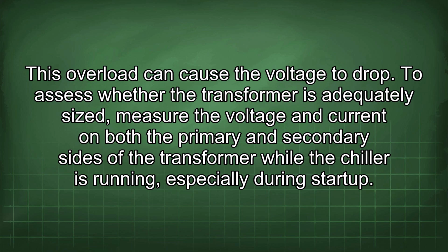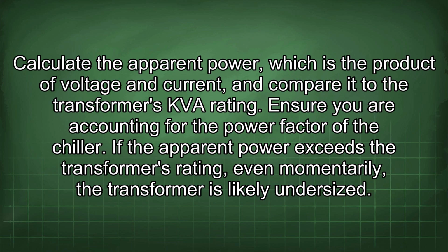To assess whether the transformer is adequately sized, measure the voltage and current on both the primary and secondary sides of the transformer while the chiller is running, especially during startup. Calculate the apparent power, which is the product of voltage and current, and compare it to the transformer's kVA rating. Ensure you are accounting for the power factor of the chiller. If the apparent power exceeds the transformer's rating even momentarily, the transformer is likely undersized.